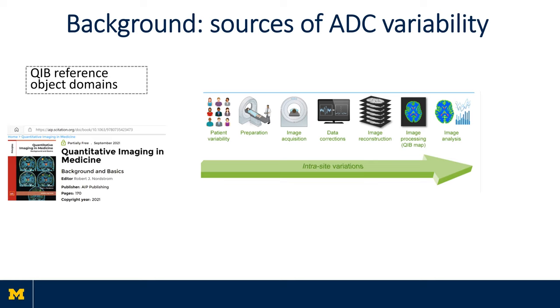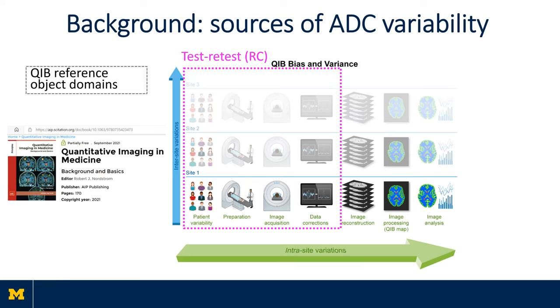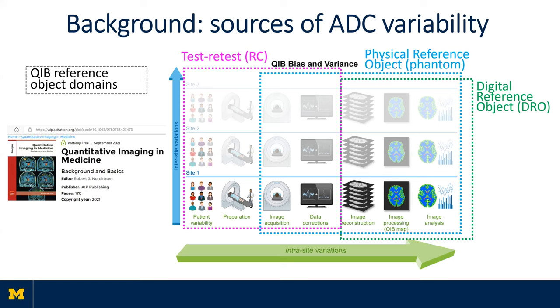Compared to familiar technical variations from scanning and analysis workflow on individual platforms, for multi-site trials there is an added dimension of cross-site variations. Test-retest studies are indispensable to characterize repeatability precision, which would otherwise be overestimated by phantoms. Physical phantoms cover a broader reproducibility landscape with particular strengths in characterizing hardware-induced variability, while DROs are best used for image analysis and parametric model evaluation.